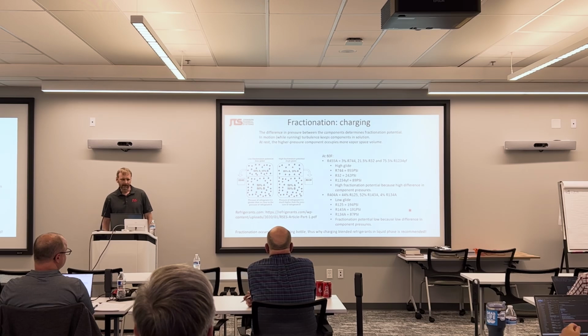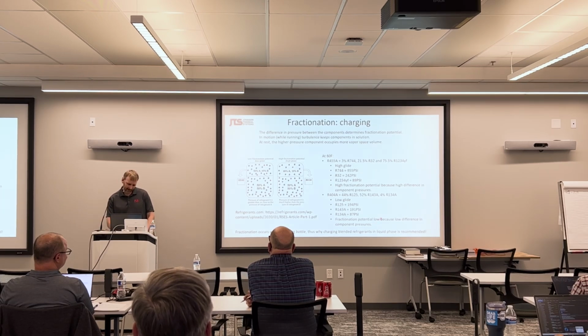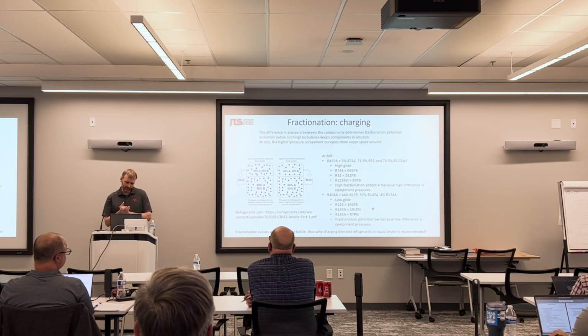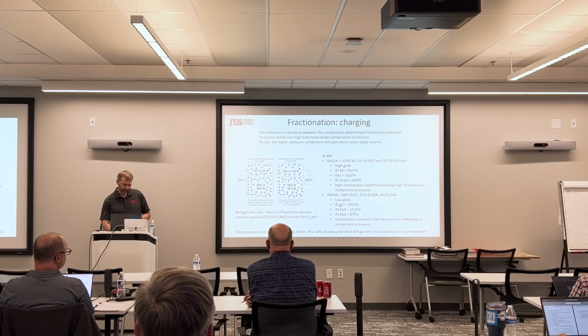Fractionation. Has anybody heard that you've got to charge with liquid when you're using blended refrigerants? Yeah? Alright, the reason they recommend this is because fractionation happens within the charging bottle. The fractionation potential is determined by the component pressures, right? So if we look at R455A, it consists of about 3% CO2, 21.5% R32, and 75.5% R1234YF.